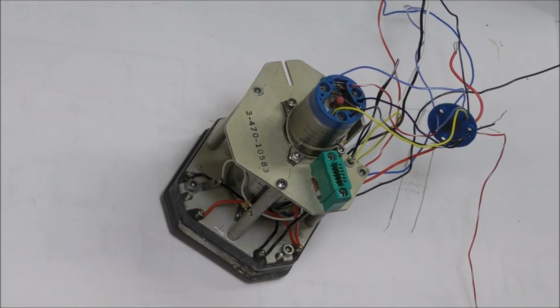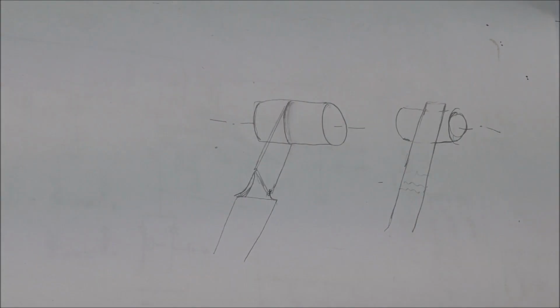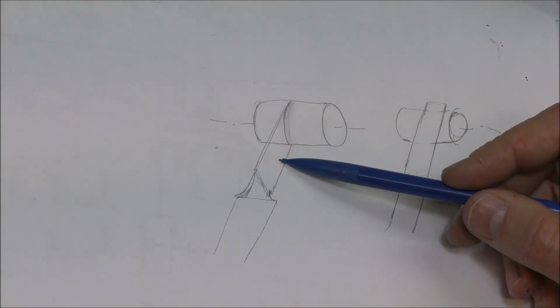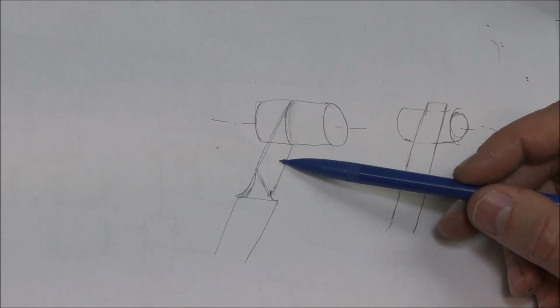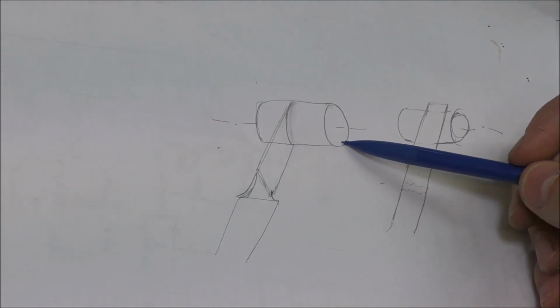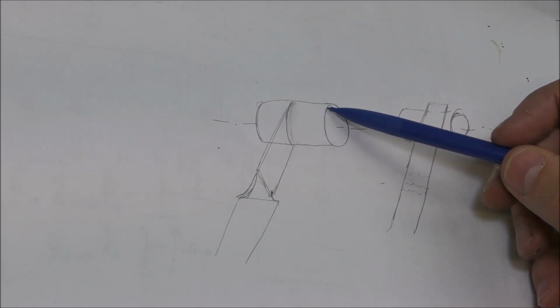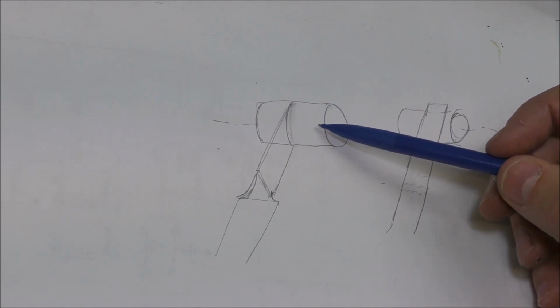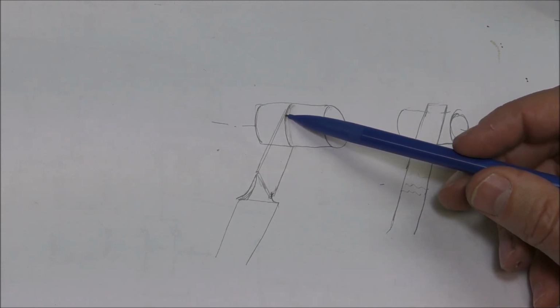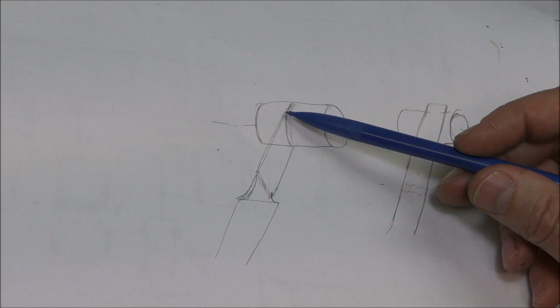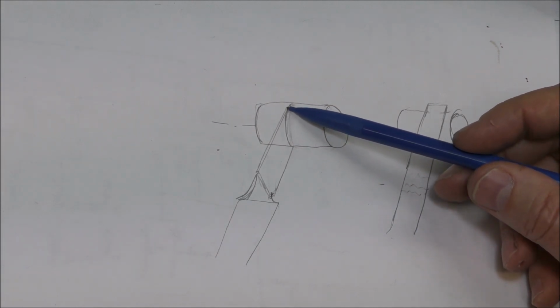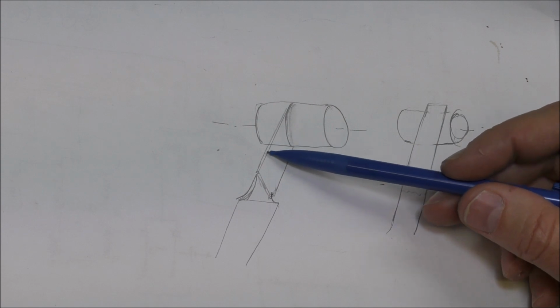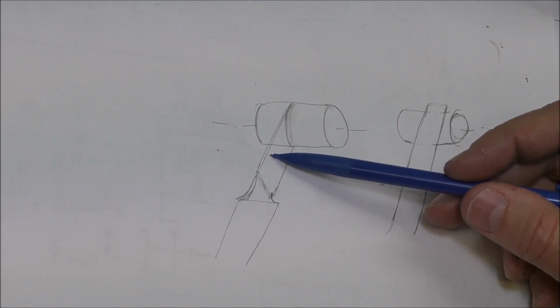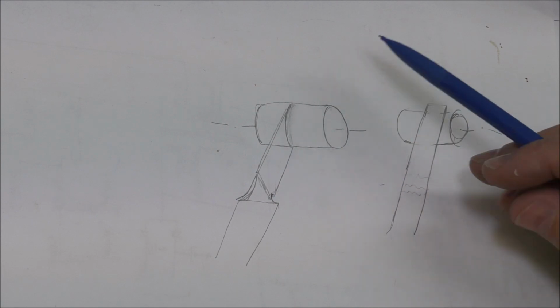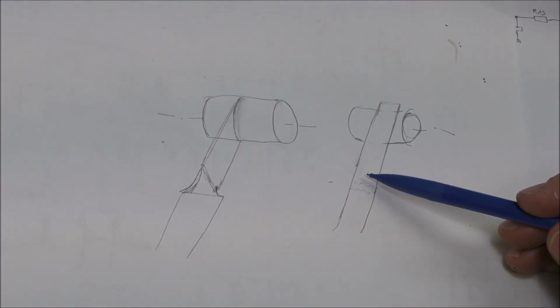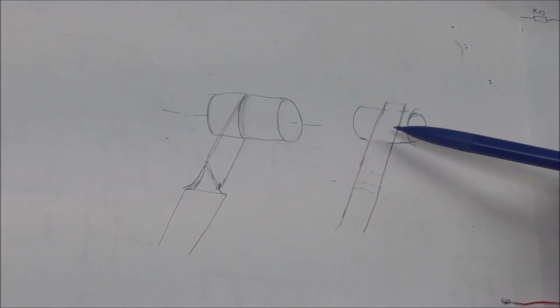So I made a repair of this synchro. So the problem was actually this contact. The original contact was like this. So this contact was perpendicular to the axis of this cylinder, contacts made with thin copper outside. And with time, after thousands and thousands of rotations, this has dug a groove in the copper, and the copper disappeared in the area of the contact. Because this contact actually is like a saw. So what I did is that I changed the orientation of the contact like this one, and this works actually.